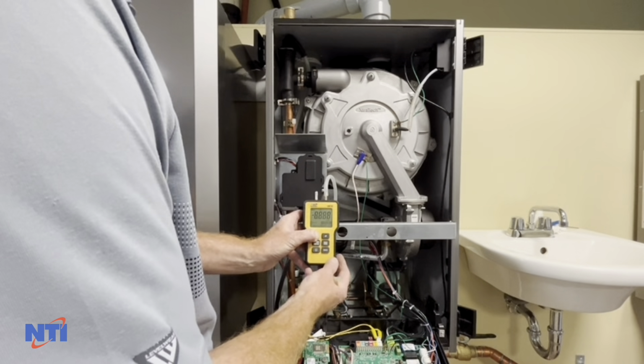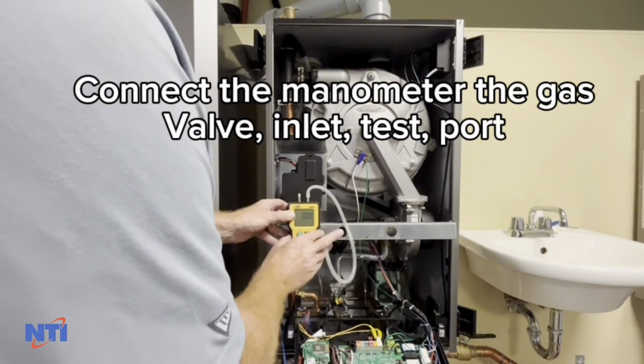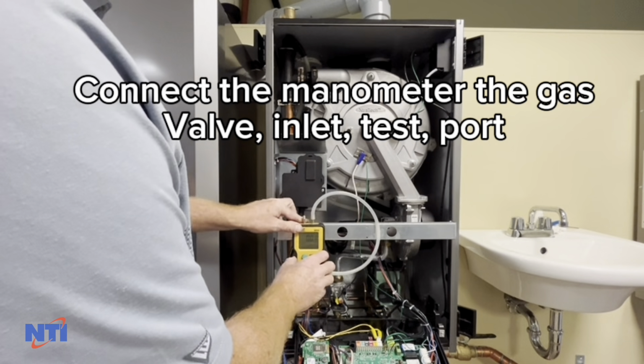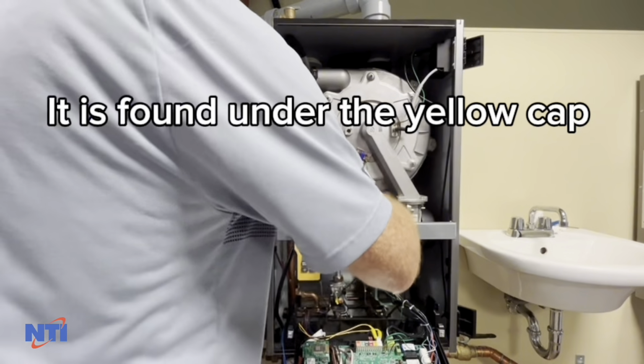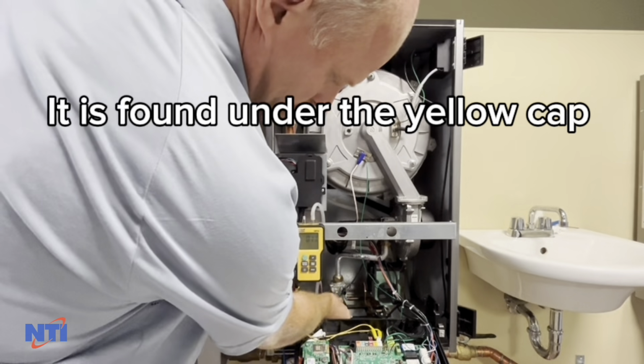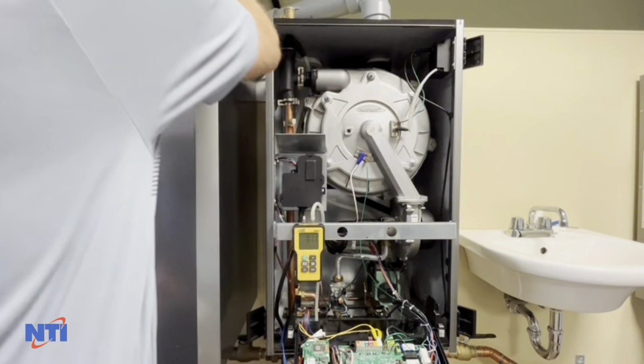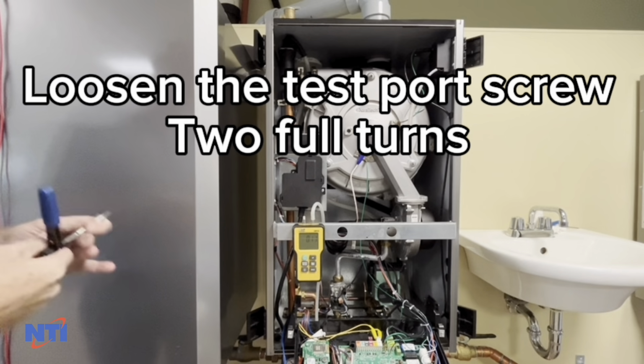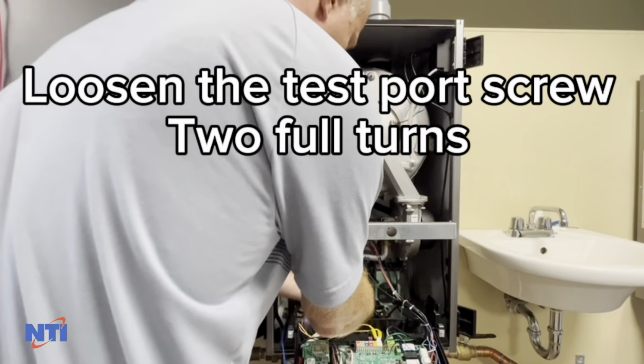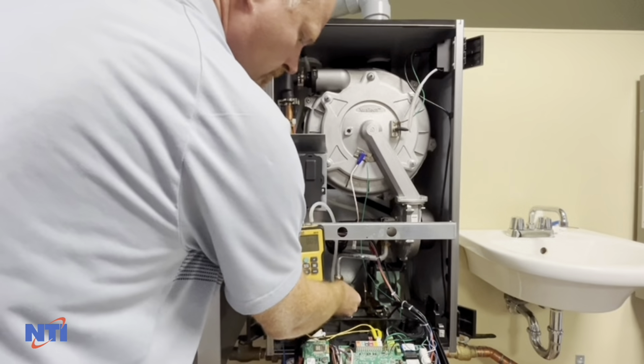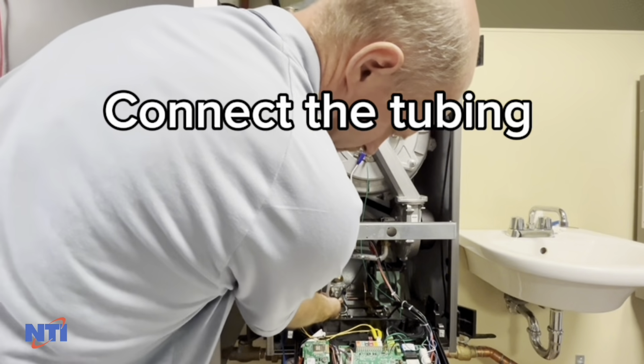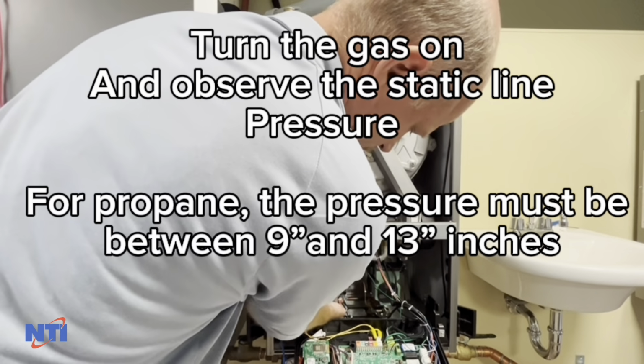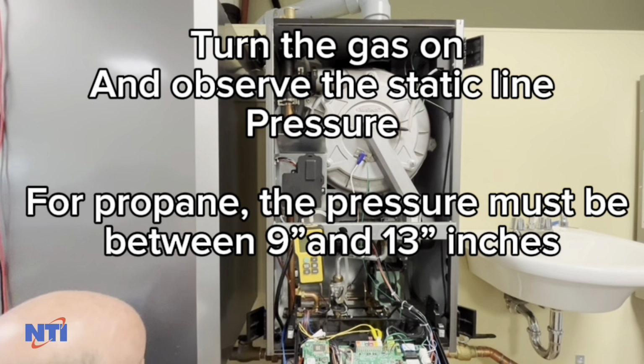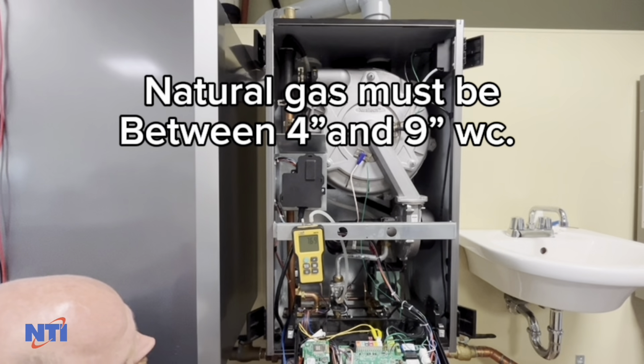Check the gas pressure on the gas valve using the line pressure test port. This port is the bottom center port. Loosen the screw 2 turns. Firmly attach the manometer and check the gas line pressure. For natural gas, this pressure must be between 4 inches to 9 inches. For propane, the pressure must remain between 9 and 13 inches.